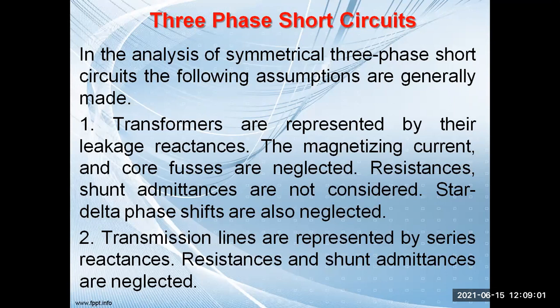First assumption: transformers are represented by their leakage reactances. The magnetizing current and core losses are neglected, so resistances and shunt admittances are not considered. Star-delta phase shifts are also neglected. This is the assumption we make when performing symmetrical fault analysis.